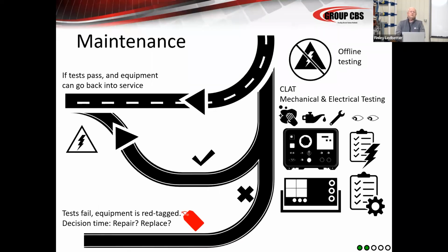So at some point, you're going to stop going around this 5 year maintenance cycle racetrack, and you're going to pull over to the side and you're going to do some maintenance. When you do here, you're going to take it offline. You're going to do some cleaning, lubing and adjusting, we hope. You're going to do some inspections, some electrical tests, some mechanical tests. And there's 2 paths here. There's the path to red tag, and there's the path right back onto the race course, okay? So when you do this testing, if, for instance, you have no problems and you encounter no issues and there are no red tags or no issues come out of the test, it goes right back into service.